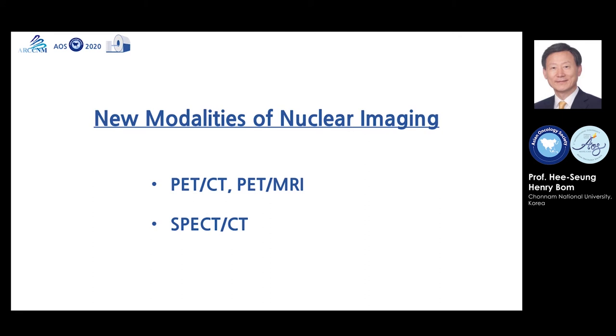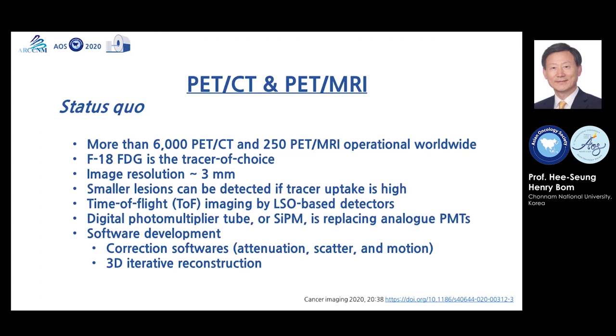Currently, more than 6,000 PET-CT and 250 PET-MRI scanners are operational worldwide, and F18-FDG is the tracer of choice. Image resolution of current PET-CT or PET-MRI is 3 mm; however, even smaller regions can be detected if tracer uptake is high. Current technologies include time-of-flight imaging, digital photomultiplier tubes, and software for correction and reconstruction.